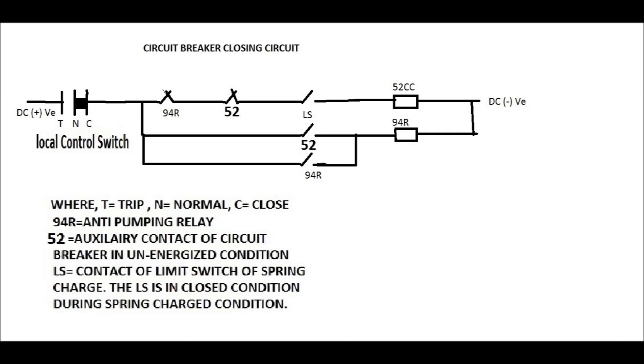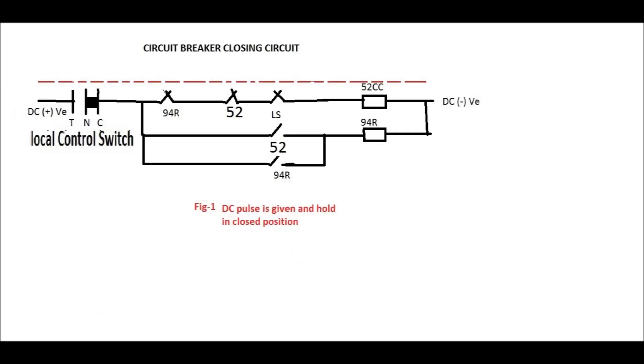To understand the function of the anti-pumping relay, let us look at the simple circuit diagram. In this diagram, 52CC is the closing coil of the circuit breaker; 52 represents the circuit breaker; 94R is the anti-pumping relay coil; and TNC is the local control switch — that is, Trip-Neutral-Close. All contacts are shown in breaker-off conditions. LS is the limit switch contact of the spring charge; whenever the spring is charged, LS remains closed. There are two auxiliary contacts of the circuit breaker: one NC in series with 52CC, and one NO in series with 94R. There are two auxiliary contacts of 94R: one NC in series with 52CC, and one 94R in parallel with 52.